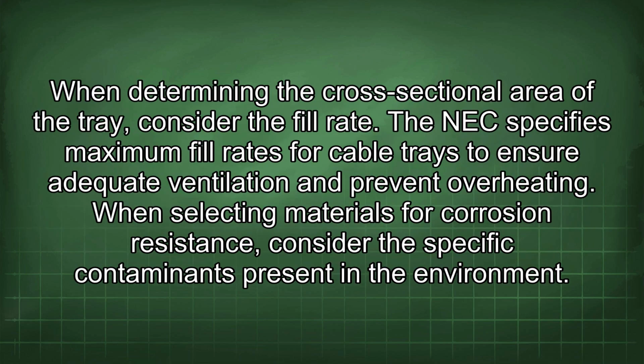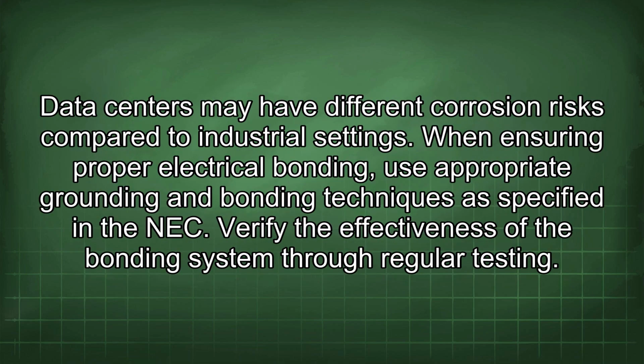When determining the cross-sectional area of the tray, consider the fill rate. The NEC specifies maximum fill rates for cable trays to ensure adequate ventilation and prevent overheating. When selecting materials for corrosion resistance, consider the specific contaminants present in the environment. Data centers may have different corrosion risks compared to industrial settings.